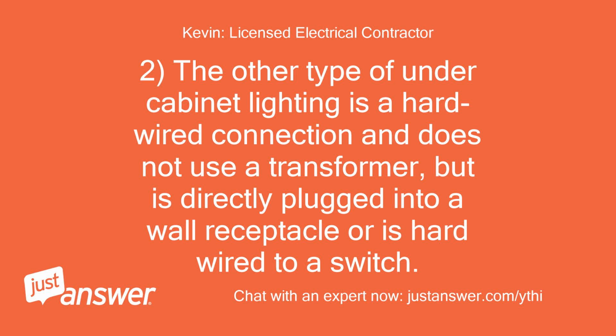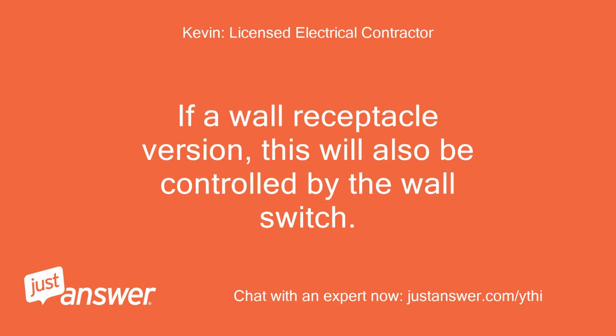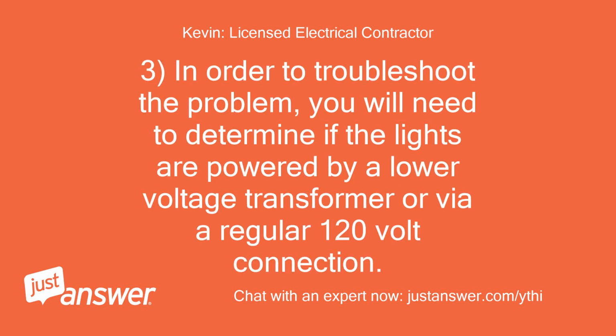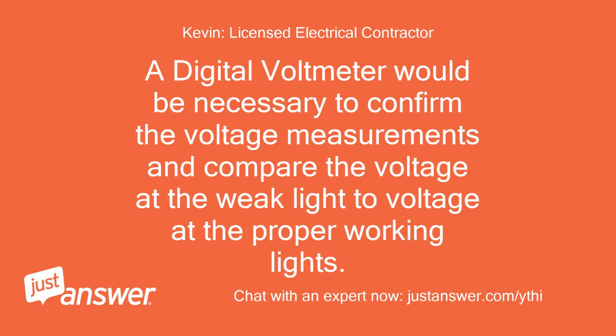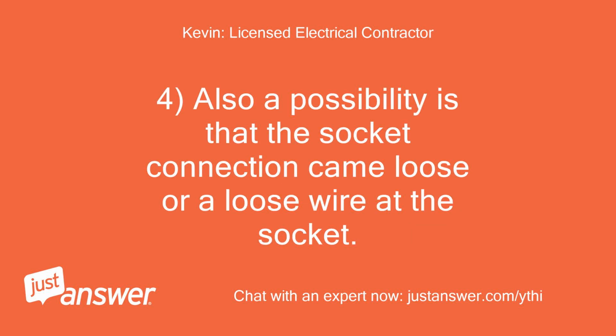2. The other type of under-cabinet lighting is a hardwired connection and does not use a transformer, but is directly plugged into a wall receptacle or is hardwired to a switch. If a wall receptacle version, this will also be controlled by the wall switch. 3. In order to troubleshoot the problem, you will need to determine if the lights are powered by a lower voltage transformer or via a regular 120 volt connection. A digital voltmeter would be necessary to confirm the voltage measurements and compare the voltage at the weak light to voltage at the proper working lights. 4. Also a possibility is that the socket connection came loose or a loose wire at the socket.